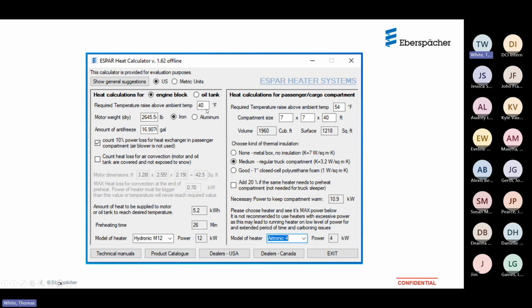If we know how much difference in temperature we want to increase, for example, in Indiana the average low temperature in January is 18 degrees. If we want to increase 40 degrees to get that up near 60, or maybe a little more, where the battery operates more efficiently than when it's colder, that's part of the calculation we can use in this calculator. And then with that information, that helps us determine what size of heater.